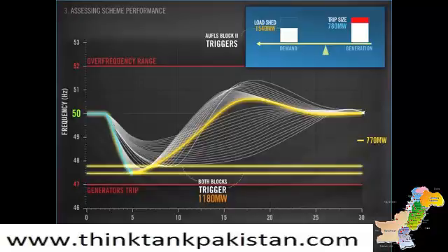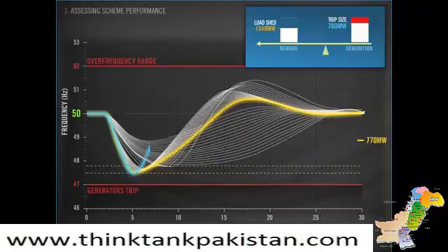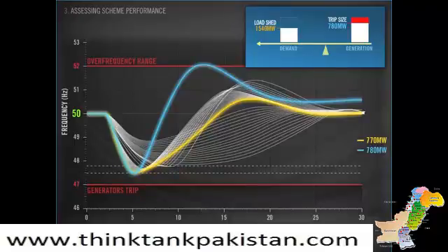From that 10 megawatt increase in trip size, we have an additional 590 megawatts of load being shed, bringing the total load shed to 1,540 megawatts. You can probably imagine what is going to happen as a result. Just as if someone jumped off the seesaw really quickly, you now have overshoot. We've reached that top limit of 52 Hz and have gone into the overfrequency range.